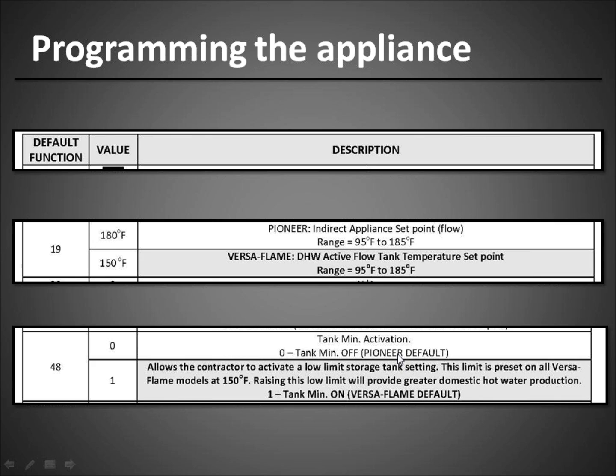There's a reason on the Pioneer that you want it active, and that's simply if you have a smaller indirect tank and you want to keep your Pioneer up to some specific temperature. So in the summertime, when your central heating shuts down, you can keep full tanks fairly warm. So, for example, if you want to keep your Pioneer at 110, so it doesn't have to go from room temperature all the way up to the full temperature required to heat up your indirect, that's the reason for that setting.